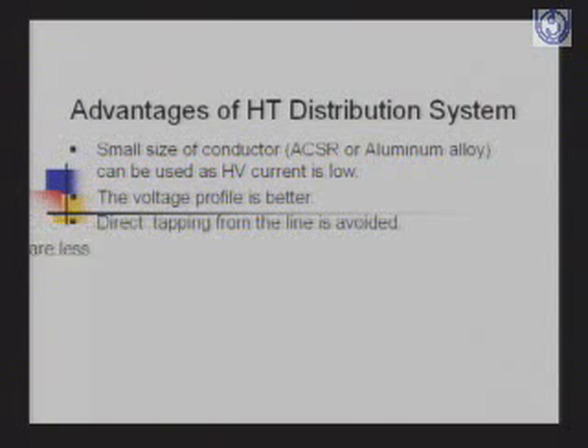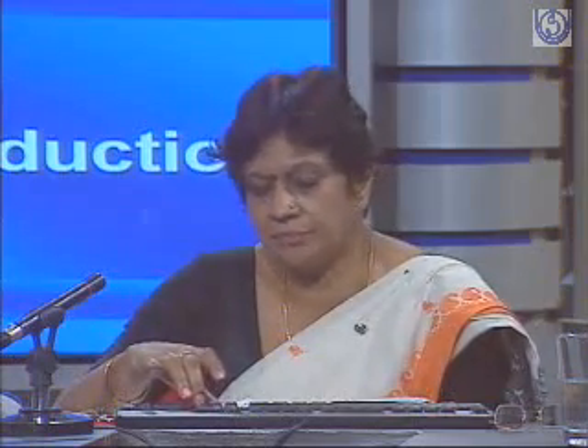The advantages of the HT distribution system are that a small size of conductor is used, because at HT, as I said, if the current in HT is 5 ampere, it will be 140 ampere in LT. The voltage profile is better, direct tapping from the line is avoided, and line losses are substantially less. People generally do not tap an 11 kV line. You have to have a transformer to tap an 11 kV line. Only then you will be able to make use of it.